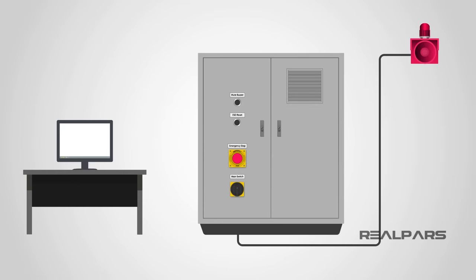So when there is an active alarm on the system and it is making that crazy loud noise, the engineer or technician can press this button to mute the buzzer and in doing so, acknowledge that they are aware of the alarm as well. Therefore, next time that you see an alarm on the HMI but there is no sound, it probably means that somebody has already acknowledged the alarm.